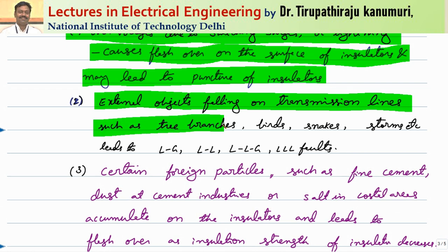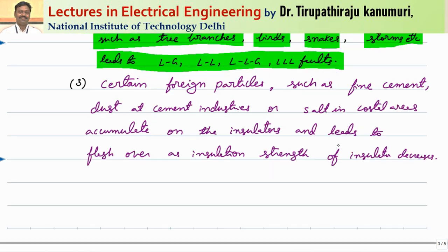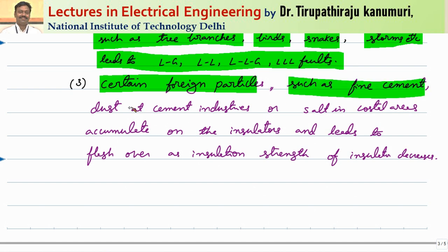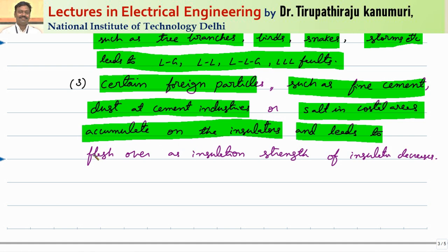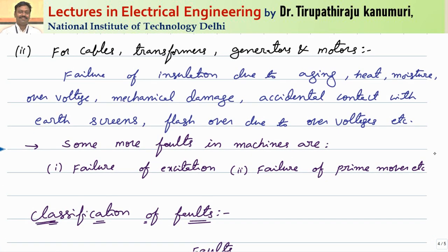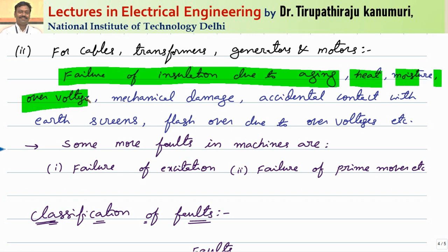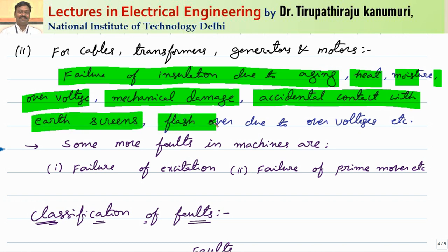Sometimes snakes are also responsible. During storms or rain, conductors will move and may lead to line to ground, line to line, LLG, or triple L faults. Another reason is that foreign particles such as fine cement dust at cement industries or salt in coastal areas accumulate on insulators and lead to flashover as insulation strength decreases drastically over time. For cables, transformers, generators, and motors, failure is due to aging, heat, moisture, over-voltages, mechanical damage, or accidental contact with earth screens.